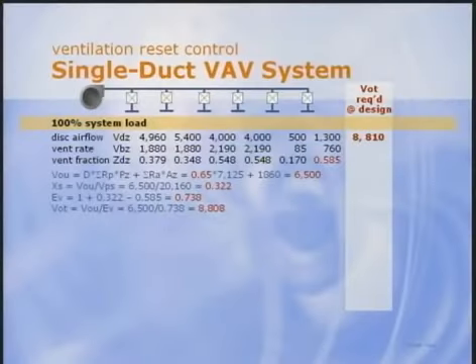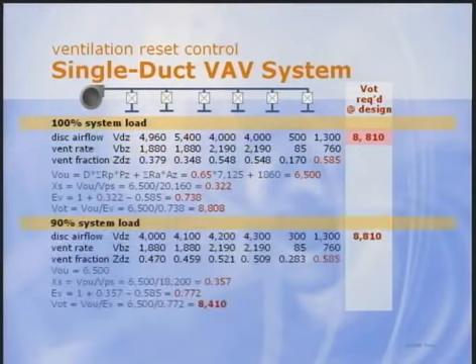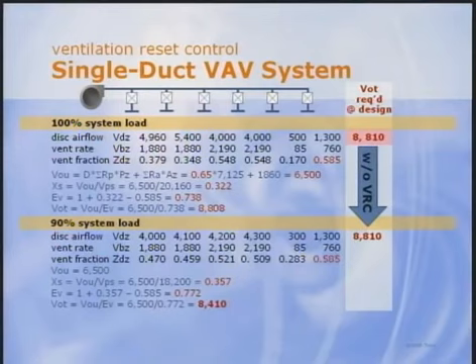Here's a single-path VAV system with 6 zones. At 100% load, we solve the multiple zone system equations to find the highest intake airflow needed, 8,800 CFM. I don't want to go through all these calculation details today. We've done that before in broadcasts and in newsletters listed in our bibliography. But notice that at 100% load, discharge airflow in some zones is at the design value, but it's lower in other zones because of load diversity.